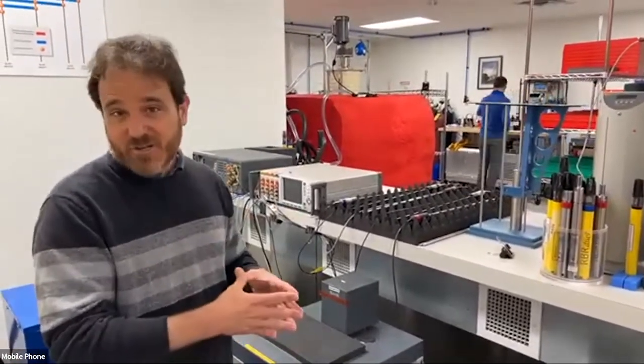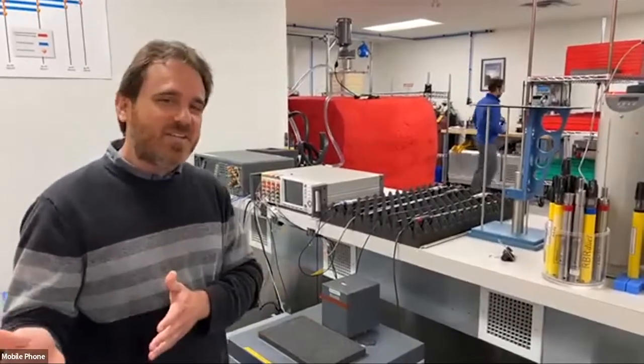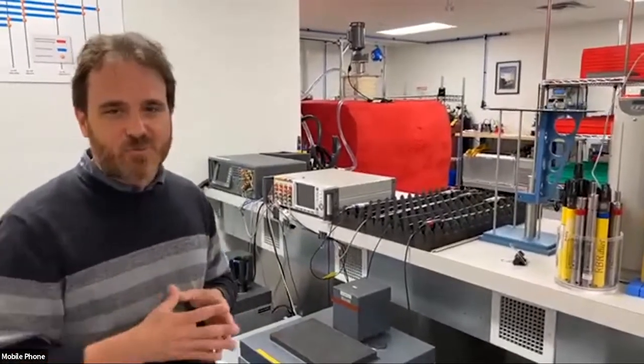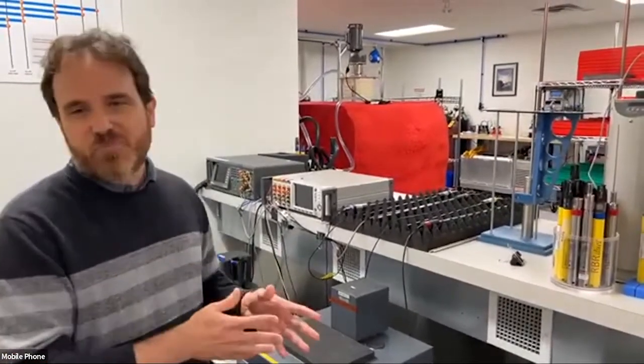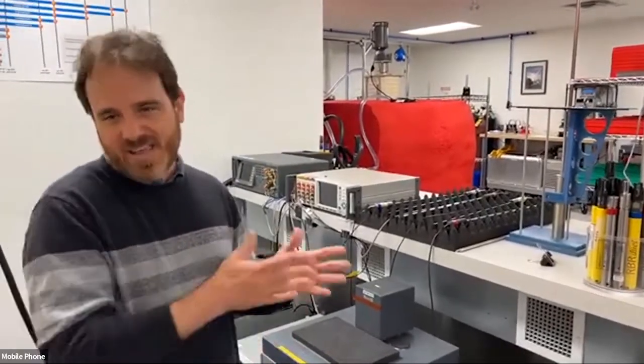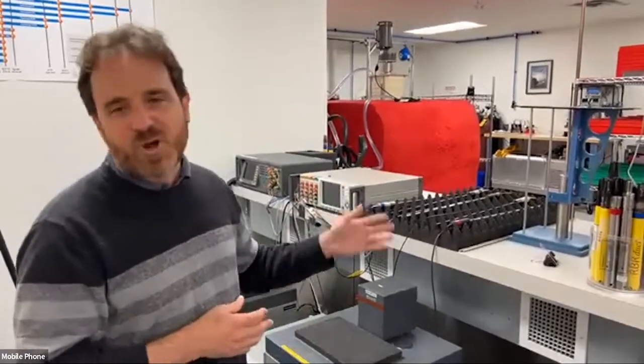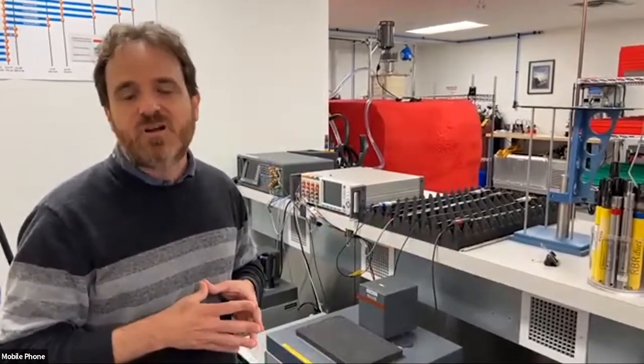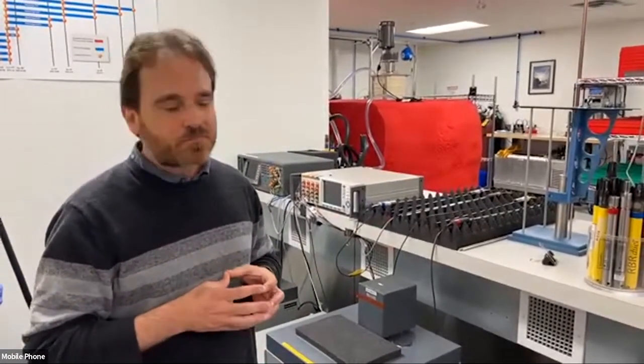Once the entire cycle is finished, we use Ruskin, our in-house developed calibration software, to process all that data, create the best fit polynomial, and adjust the instrument as per the reference readings that we obtained from our reference thermometers.